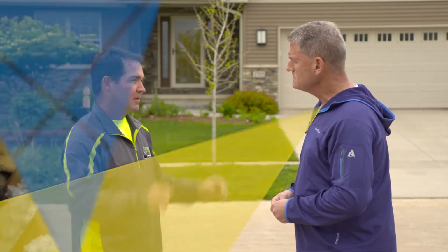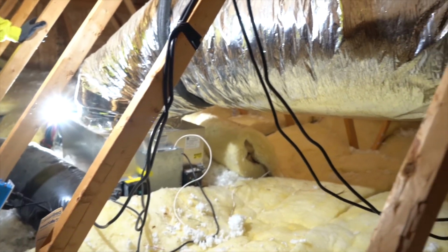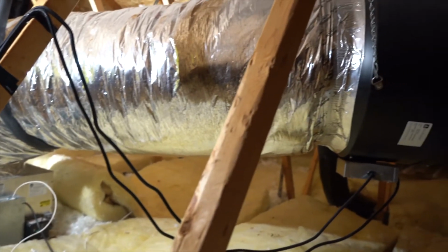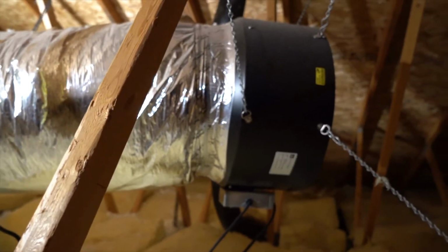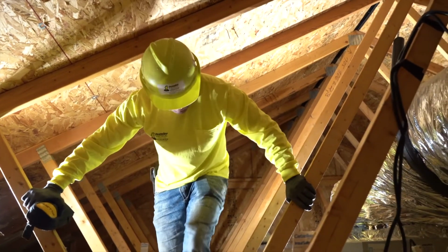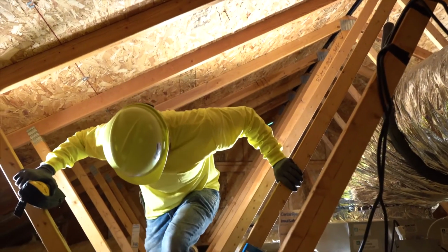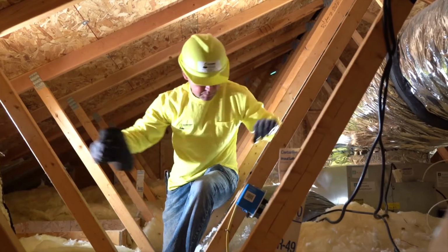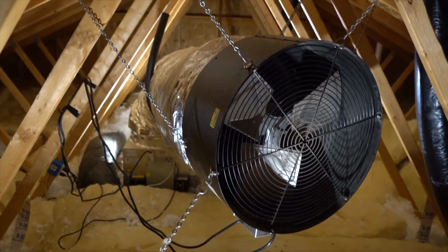You build a frame for installation of the dampers, and then the fan itself sits up in the attic, supported through the trusses. From an electrical standpoint, we provide power, usually just through an outlet controlled by one of the means I mentioned: thermostat, timer, or a simple light switch. You fire it up and away it goes.